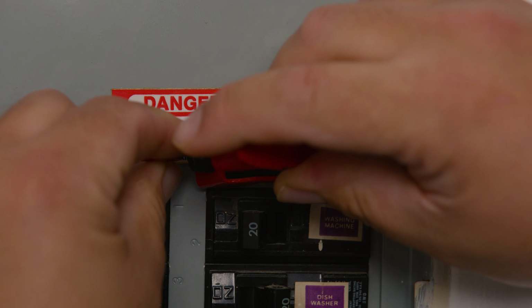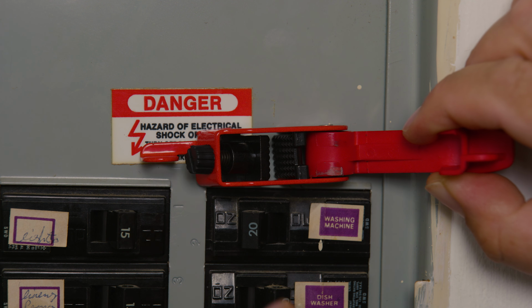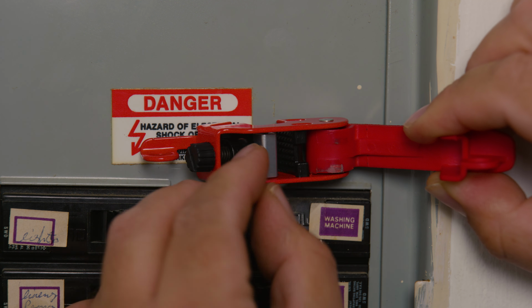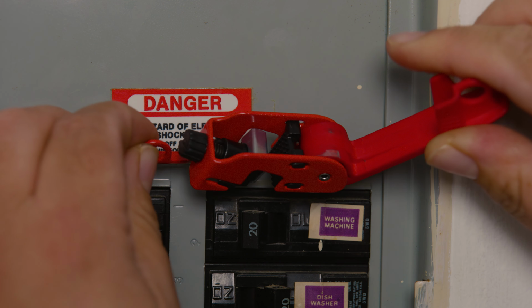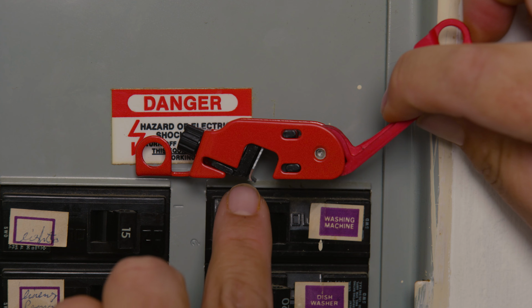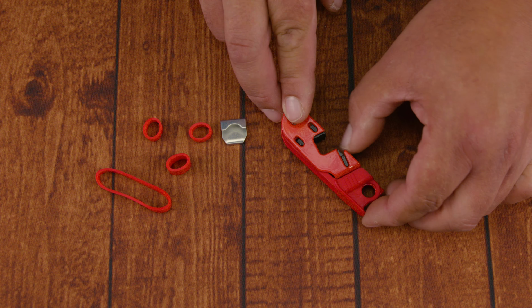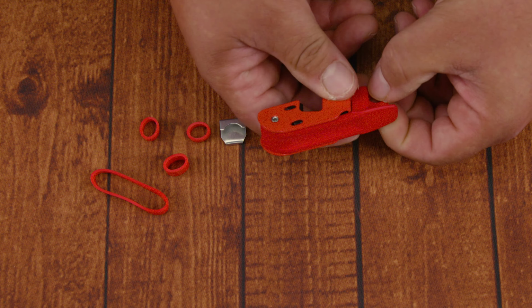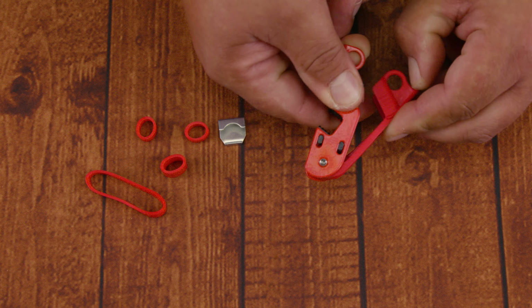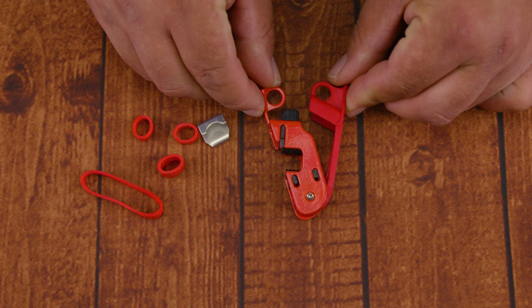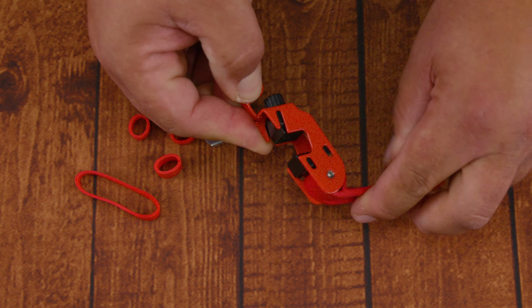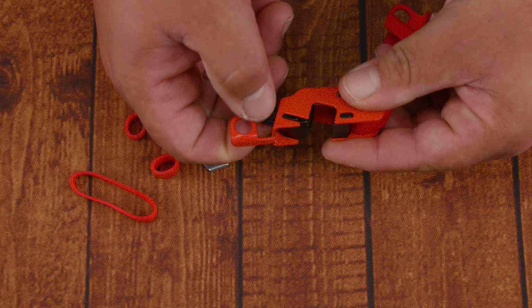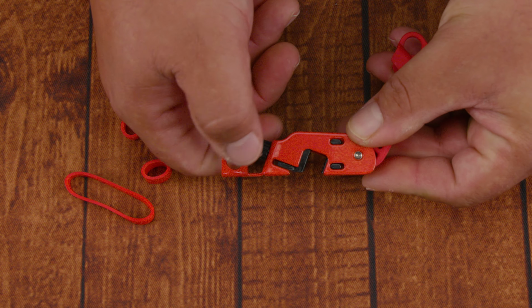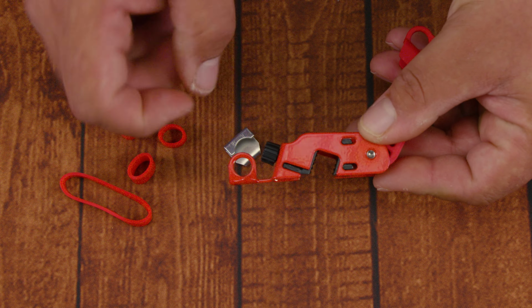And when we're using the metal clip, what you want to do is install it on the side of the knob where the grip is located at, and you're going to notice that the tab will be at the bottom, so when you tighten the grip it would hold down the metal tie bar, therefore locking out your double or triple circuit breaker. But all these accessories are optional, and this basically works by opening the toggle, and if you notice on the inside you're going to notice two grips that as you turn the knob clockwise it would tighten to hold the circuit breaker toggle. And once the grip is tightened on the toggle, we can close the lockout, and you'll notice at the end a hole to place your lock or your zip tie.